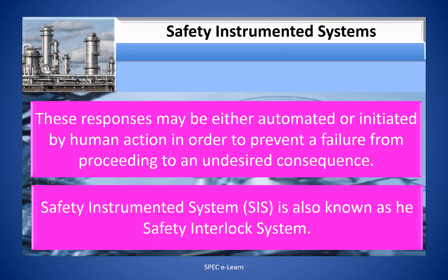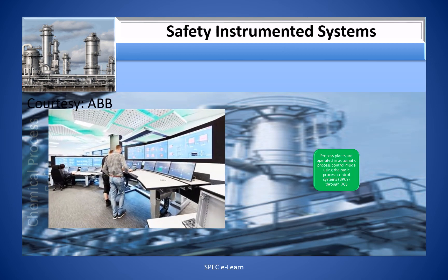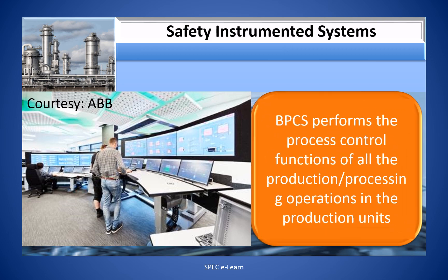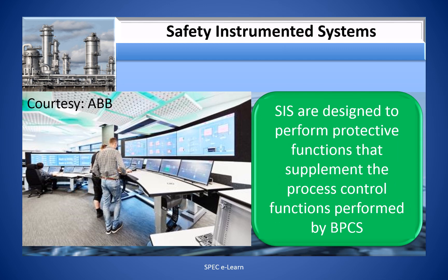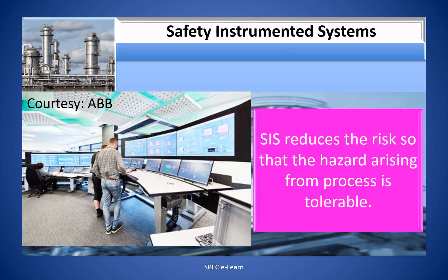Safety Instrumented System is also known as Safety Interlock System. Process plants are operated in automatic process control mode using the Basic Process Control System, BPCS, through DCS. BPCS performs the process control functions of all the production and processing operations. SIS is designed to perform protective functions that supplement the process control function performed by the BPCS, reducing the risk so that the hazard arising from the process is tolerable.